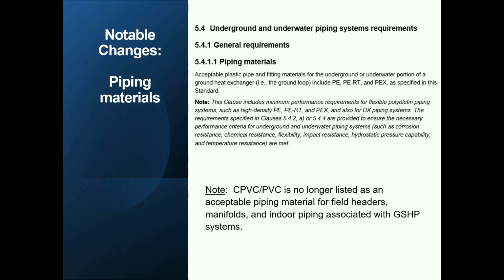Same idea, right, you're fusing them, but unfortunately the chemicals within the antifreeze agents can break down those seals. So there's been a lot of heartache in the industry, north and south of the border. The piping committee, made up of really knowledgeable people, said this is not a good thing to have in these ground source heat pump systems, so it's no longer standard compliant.